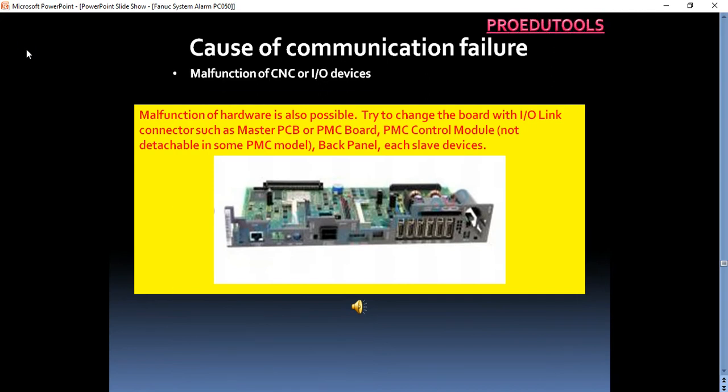Malfunction of CNC or IO devices. Malfunction of hardware is also possible. Try to change the board with IO link connector such as master PCB or PMC board, PMC control module not detachable in some PMC model, back panel, each slave devices.